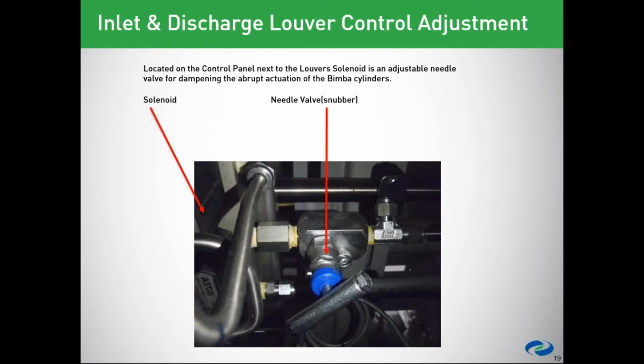Now, you don't want to over-adjust this. Basically, it needs to make some noise when it opens and closes. Because of the speed of closing, it may not close completely. And we find in colder weather that if it's open at all, the inside of that compressor gets very, very cold.